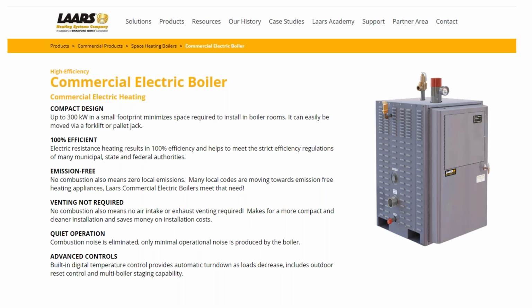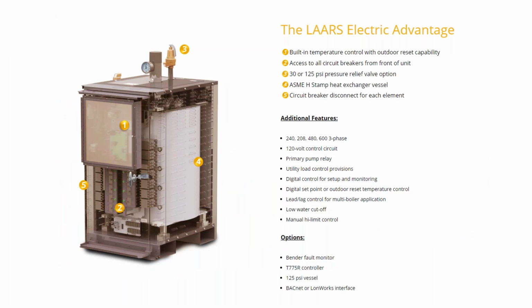Very quiet operation, you only hear switching going on, and the advanced controls create a turn-down and turn-up scenario where it only turns on the amount of heat elements you need for each type of application. As you can see, the internals are a very simple design with the switchboard and everything in the front. It has outdoor reset capability and temperature controls, and it can be set up with a 30 or 125 psi pressure relief valve option. And there is an H-stamp. These are H-stamp heat exchangers.